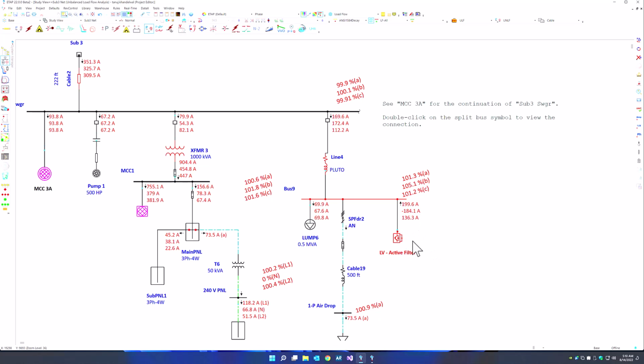Once the rating limit of the filter is met, there's no more unbalanced correction possible. So you can essentially use this new element to go ahead and look at your distribution system and use active filters to compensate unbalance or power factor correction as needed.